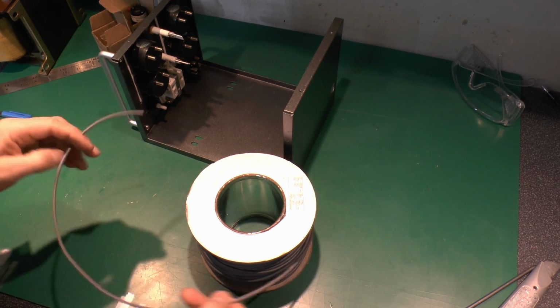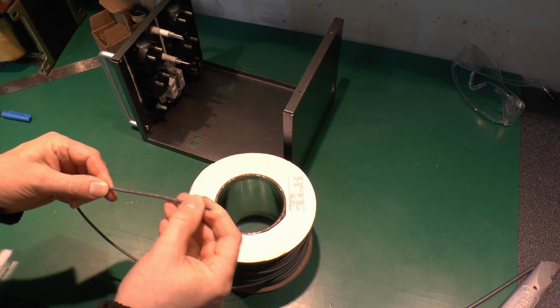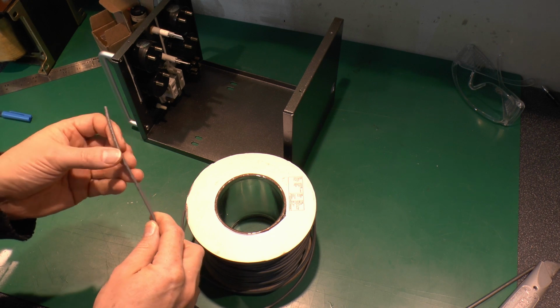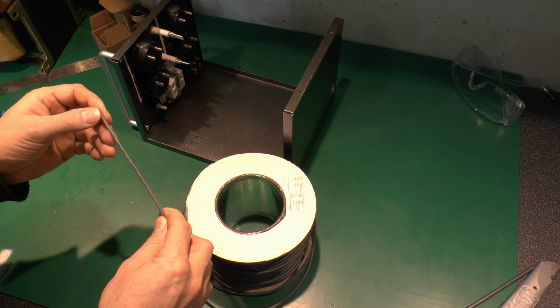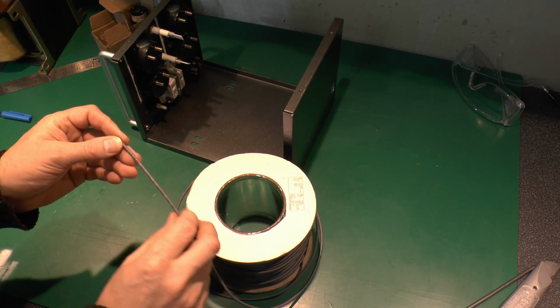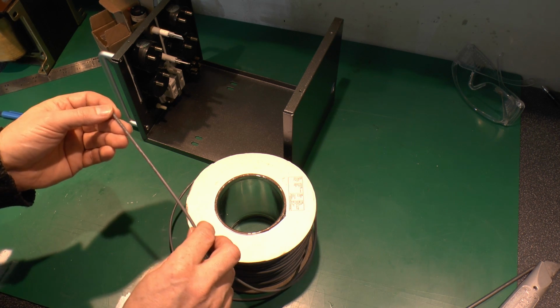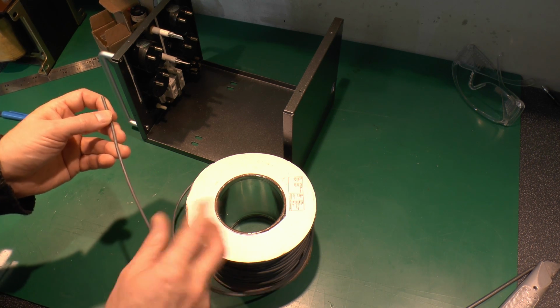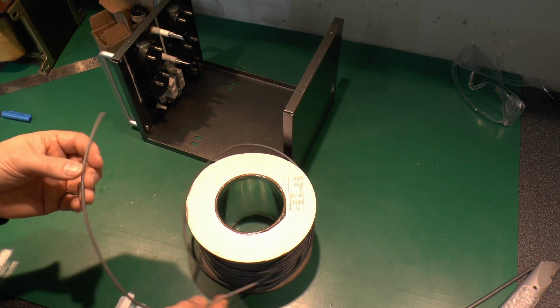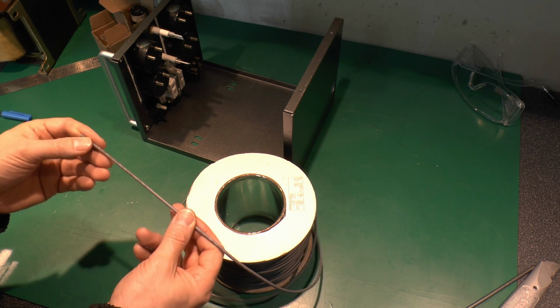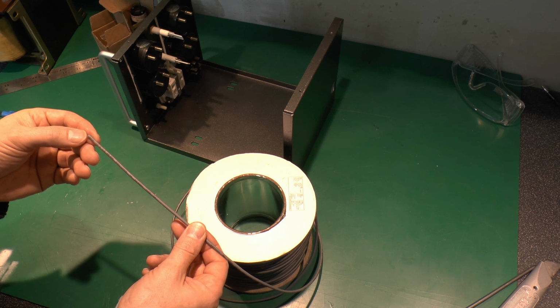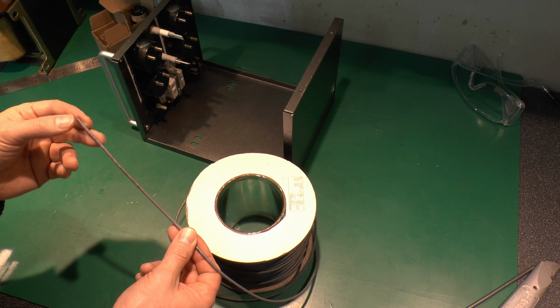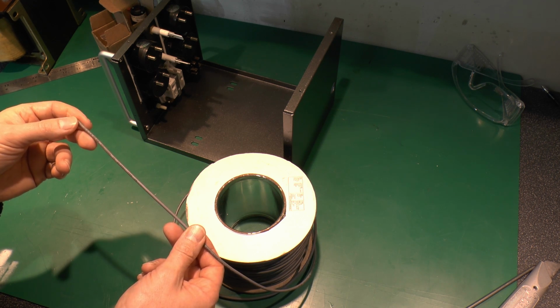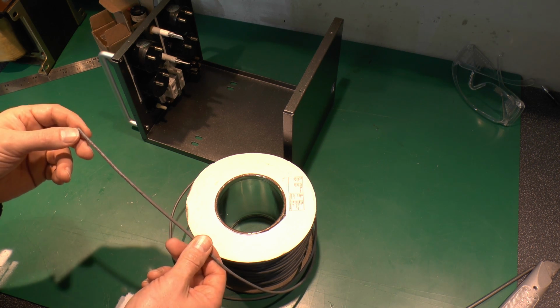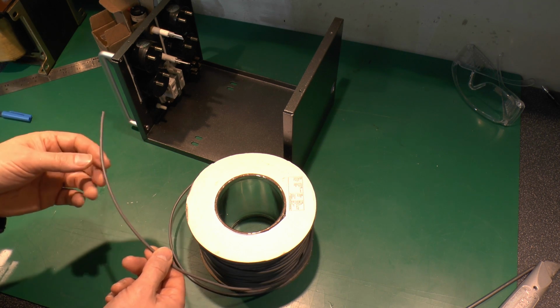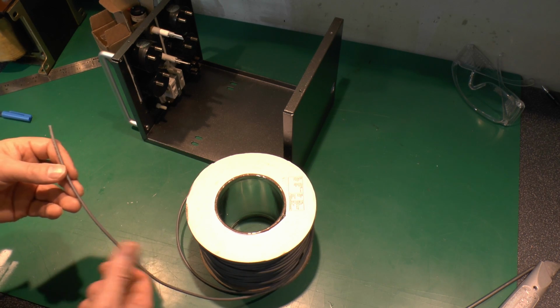Now for the internal wiring we're going to use this, which is 1.5 millimeters squared, or square millimeters, depending on how you want to pronounce that. It says square millimeters on here, and this is what's called tri-rated, meaning it complies with 3 different standards, so you can use it in different countries, North America being one of them. This is somewhat oversized for this thing, but I think it's better to go slightly larger than undersized. It's also rated to 90 degrees centigrade, so fairly high temperature, because transformers by their nature do get hot when in use.